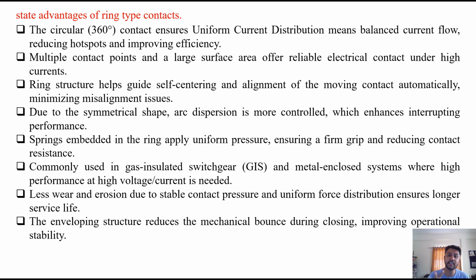Due to the symmetrical shape, arc dispersion is more controlled because it is symmetrical on all sides, which enhances interrupting performance. Springs embedded in the ring apply uniform pressure, ensuring a firm grip and reducing contact resistance. Commonly used in gas-insulated switchgear and metal-enclosed systems where high performance at high voltage and current is needed. Less wear and erosion due to stable contact pressure and uniform force distribution, ensuring longer service life. The enveloping structure reduces the mechanical bounce while closing, so it improves the operational stability. So there are several advantages of ring type contacts of a circuit breaker, and due to this it is very much used for high current applications.